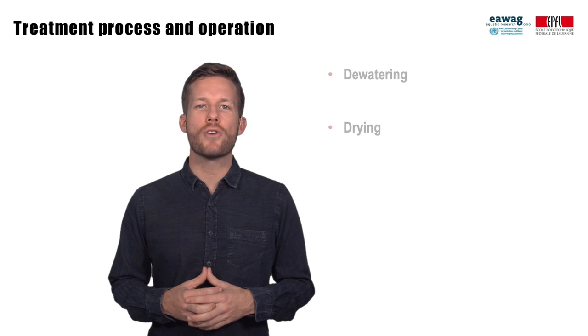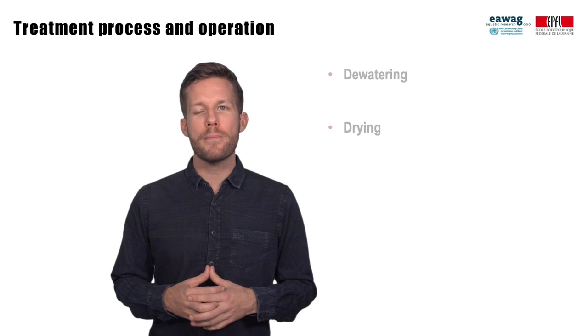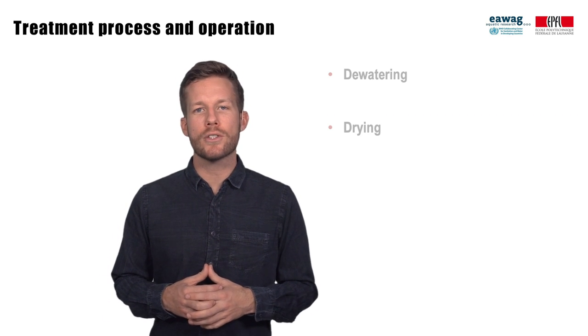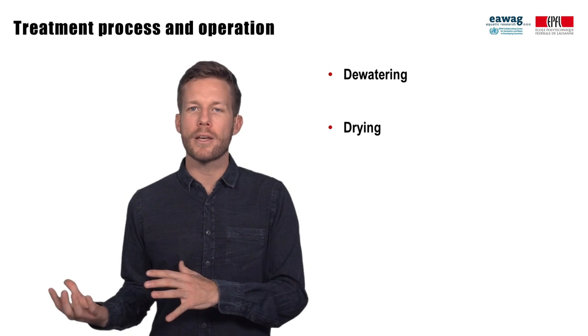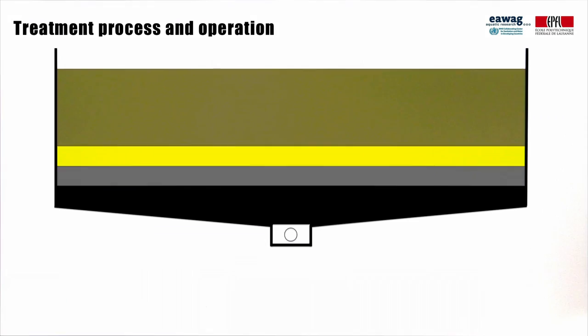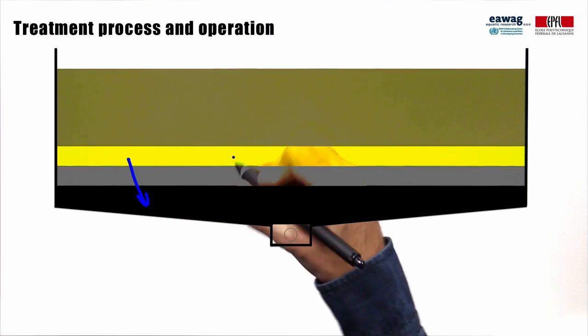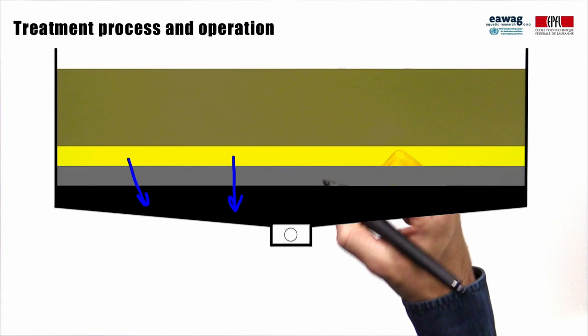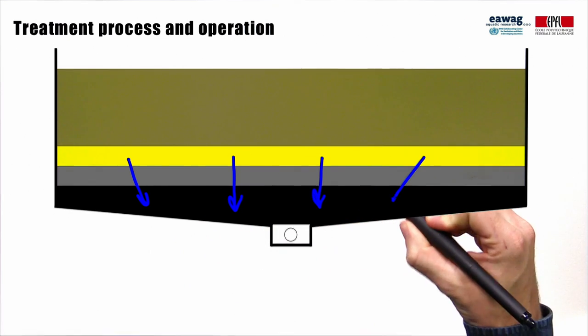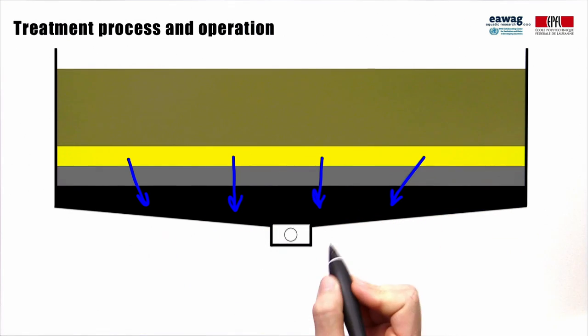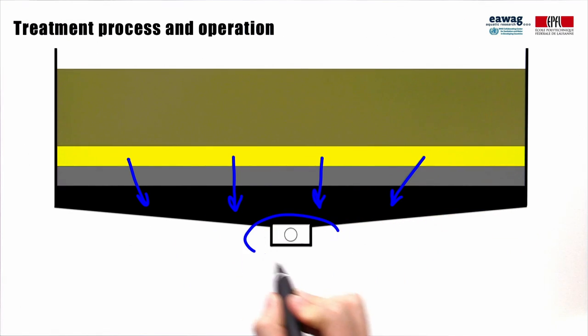The treatment process on drying beds can be separated into two stages: dewatering and drying. During dewatering, liquids and solids are separated by filtration. The free water in sludge percolates through the sand and gravel filter layers and is collected at the bottom with a drainage pipe for further treatment.